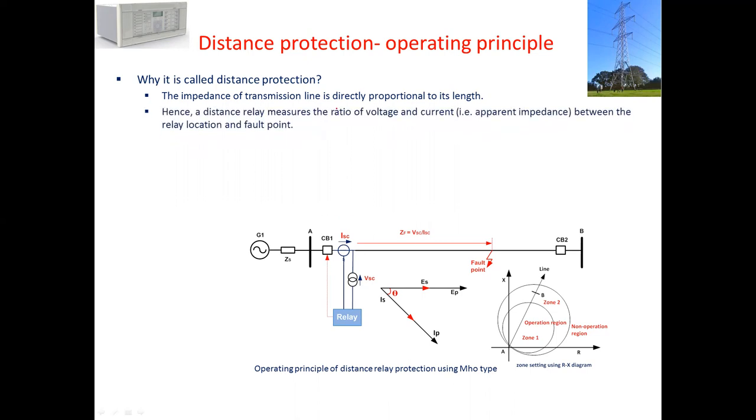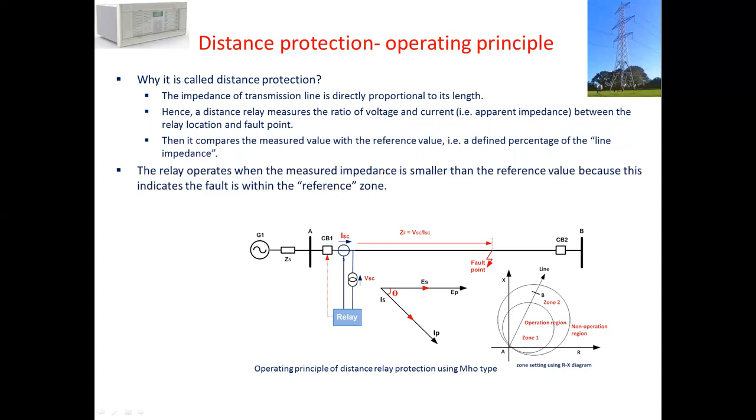A distance relay measures the ratio of the voltage to the current. When there is a fault, it measures the ratio of the voltage to the current. That is called apparent impedance between the relay location and the fault. It compares the measured value with the reference value and operates when the measured impedance is smaller than the reference value or the actual value, because this indicates the fault is within the reference zone.